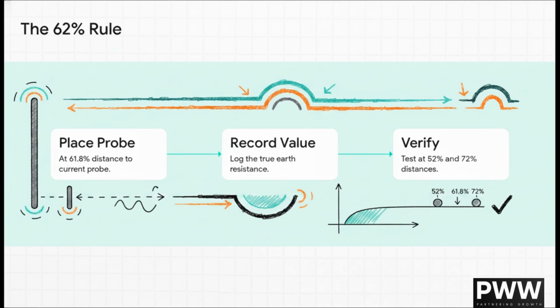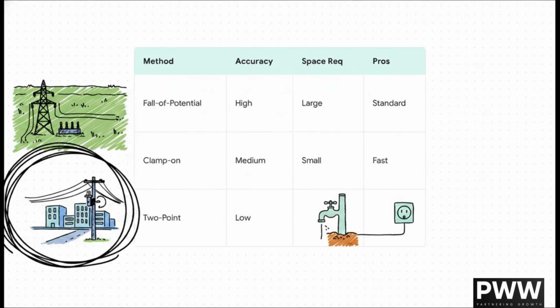measurement is solidly valid. Look, the real world rarely hands you a perfectly flat, wide-open field, right? For a new large substation, fall of potential is highly accurate, sure, but it requires massive space and full system disconnection. What if you're in a heavily paved urban area? You might opt for the clamp-on stakeless method. It's incredibly fast and non-invasive, but remember, it literally only works on multi-grounded systems where a parallel return path actually exists. The two-point dead earth method is another fallback, using a known good ground like a municipal water pipe. But it's much less accurate because it lumps in the resistance of the return path itself. You really have to select your method based on the reality of your site.